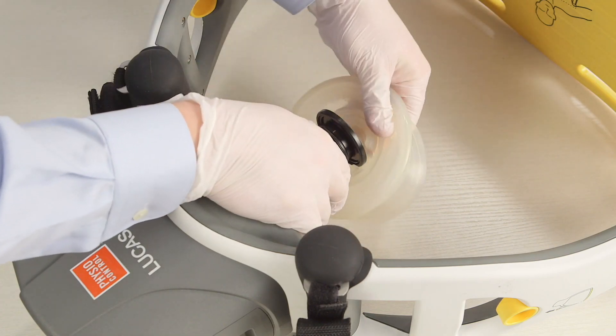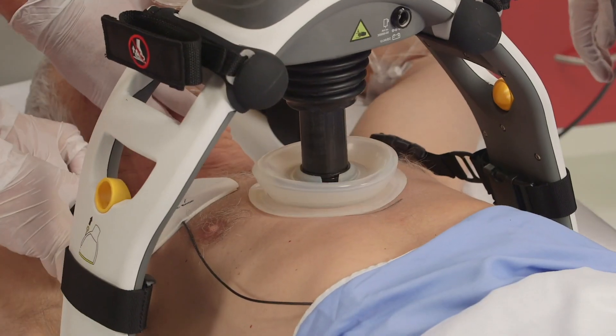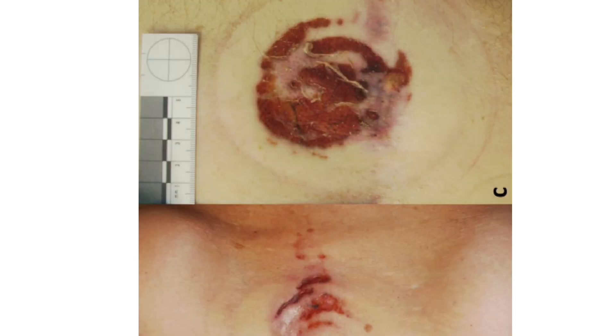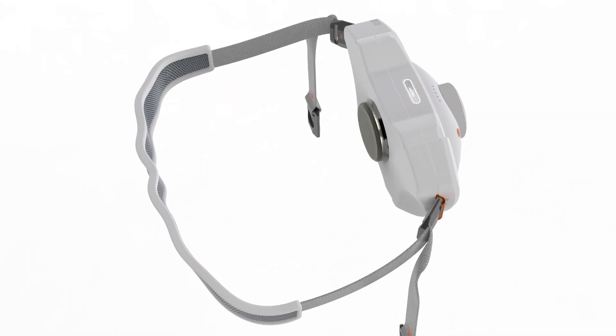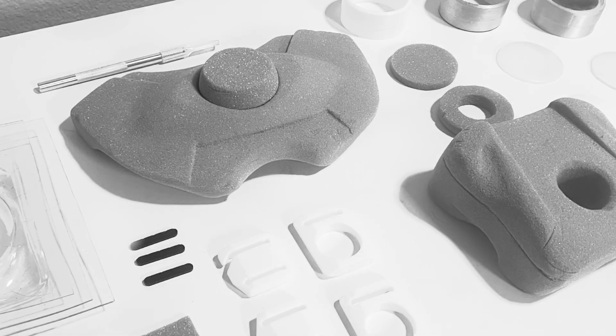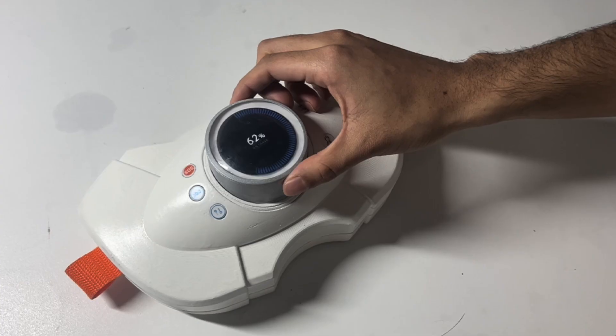In the Lucas CPR device, a suction cup on the linear rod's ends contacts the skin only at the edges, causing pressure points and marks. To address this, we tested various materials and found microfiber to be optimal. When used with full contact on the skin, microfiber reduces the pressure without deforming. Our design is cost effective, with a bill of materials at $200, and is lightweight and portable.